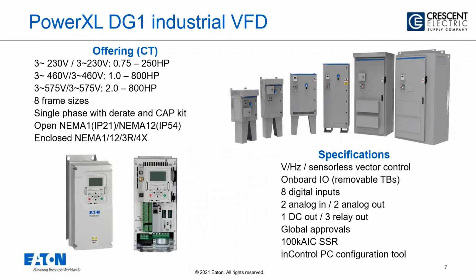We do as well have an enclosed offering, and this will be our PowerXL DG1, our general purpose industrial drive. This as well is a constant torque rated device. And we have this ranging in the 230 volts up through 250 horsepower, and our 460 and 575 up to 800 horsepower. We can do single phase on this, so we can come in at single phase and go out 3 phase. It does do a phase conversion. You can do that with or without an external capacitor kit.